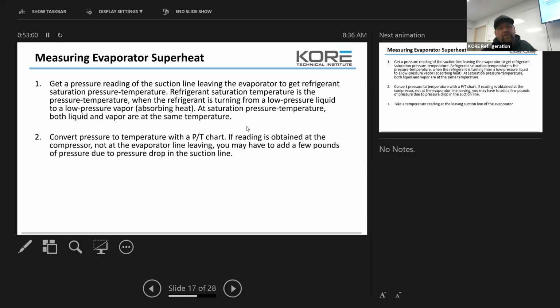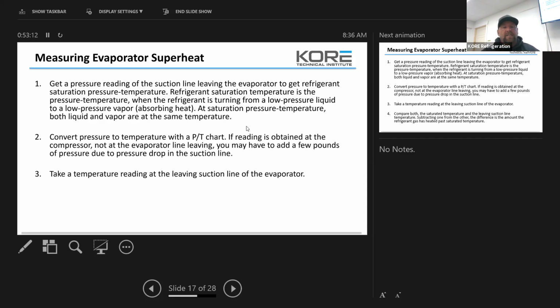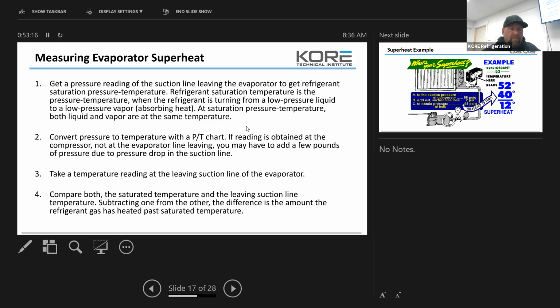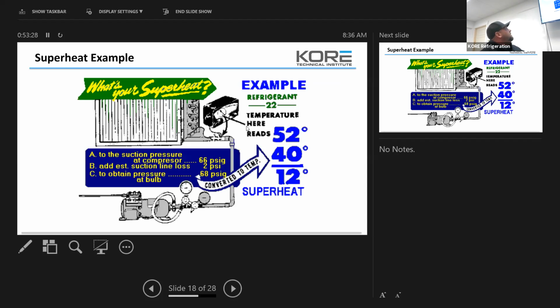Convert pressure to temperature with a PT chart. If the reading is obtained at the compressor, not at the evaporator line leaving, you may need to add a few pounds of pressure due to the pressure drop in the suction line. Just talked about that. Take a temperature reading at the leaving suction line of the evaporator. Compare both the saturated temperature and leaving suction line temperatures, subtracting one from the other. The difference is the amount the refrigerant gas has heated past the saturated temperature.